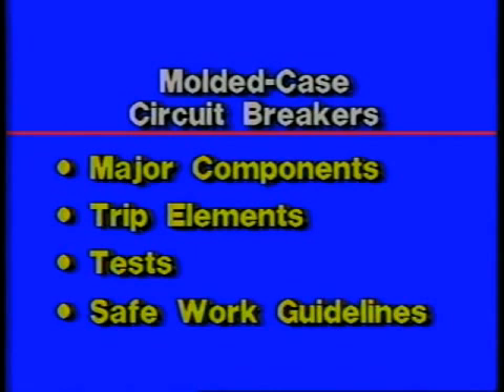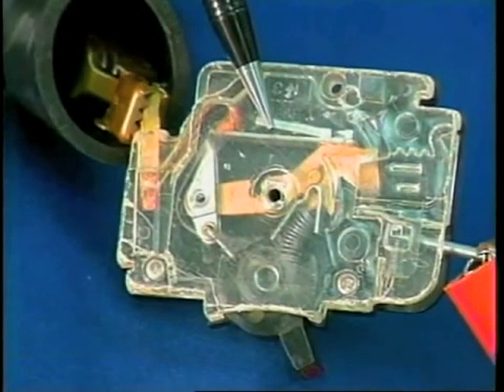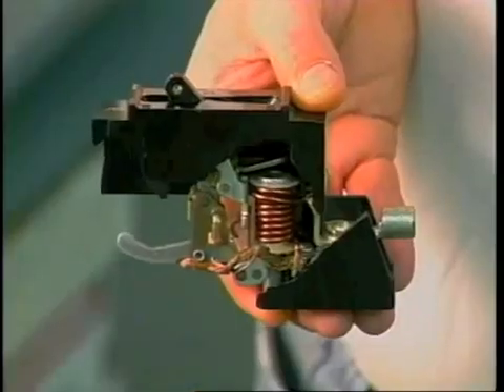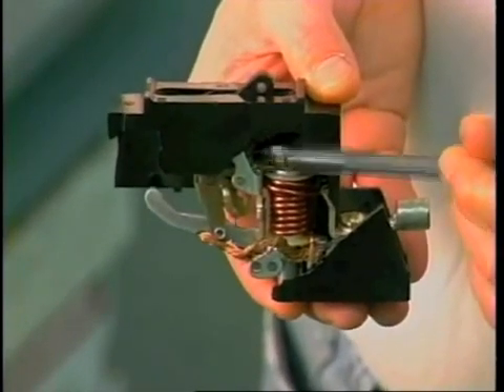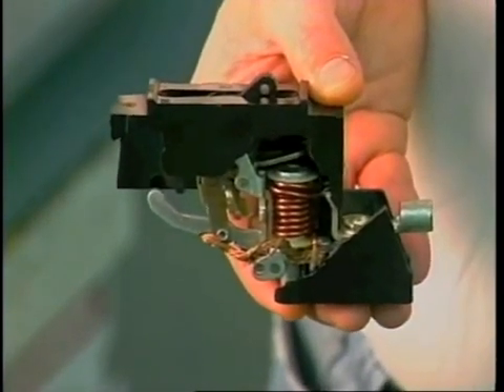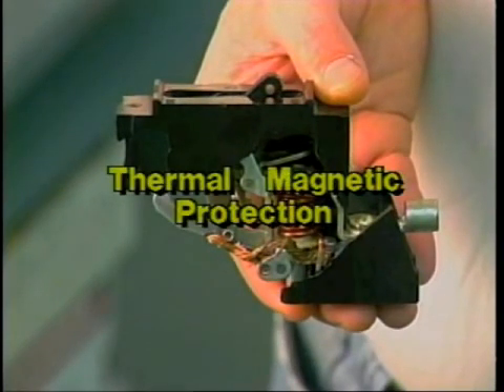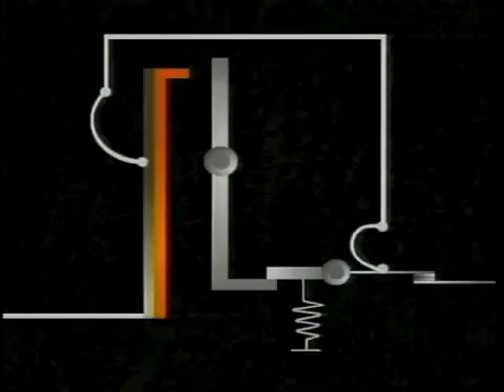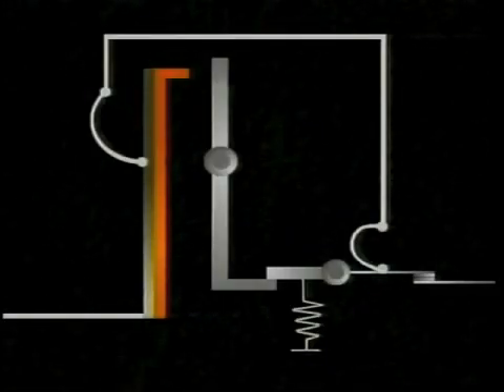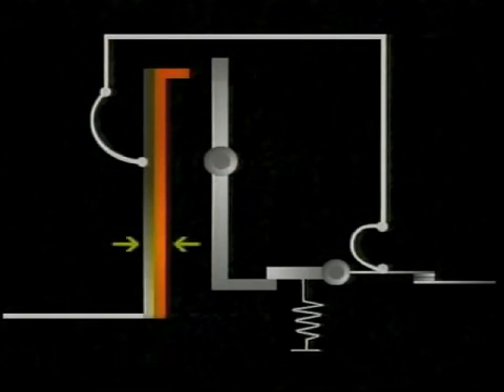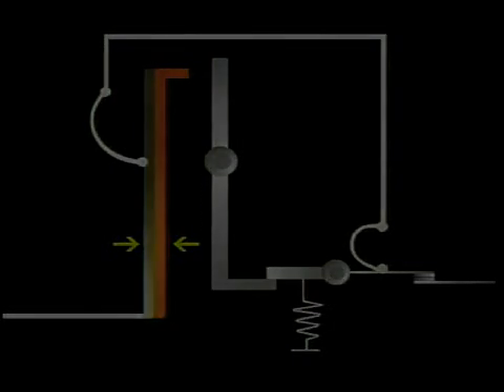type of equipment. The trip element on a conventional breaker uses bimetallic and electromagnets to provide overload or short circuit protection. This type of protection is called thermal magnetic protection and is an industry standard. Let's look at both the thermal and the magnetic operating positions of the trip element to see how they work. Thermal trip action is achieved through the use of bimetal strips heated by the load current. A bimetal strip consists of 2 strips of dissimilar metal bonded together.